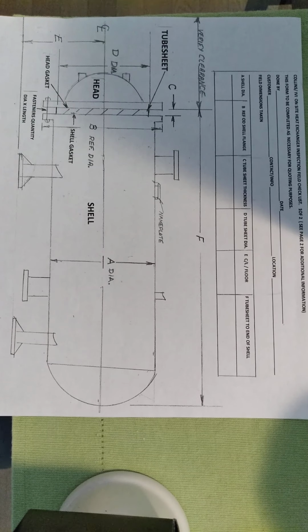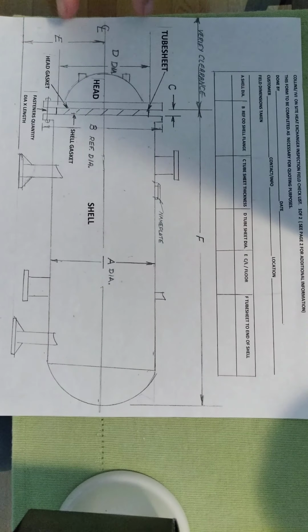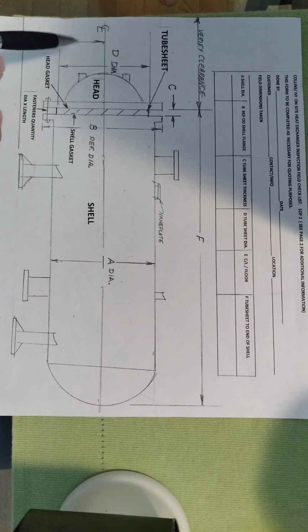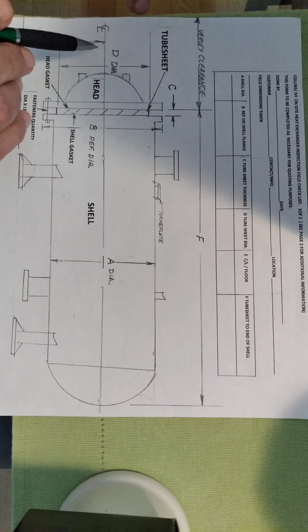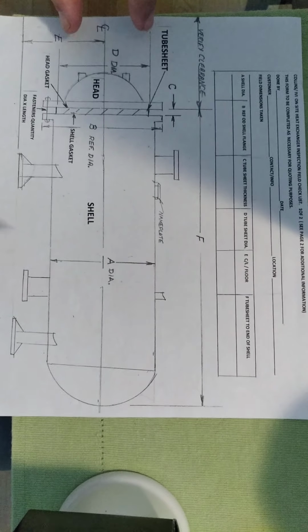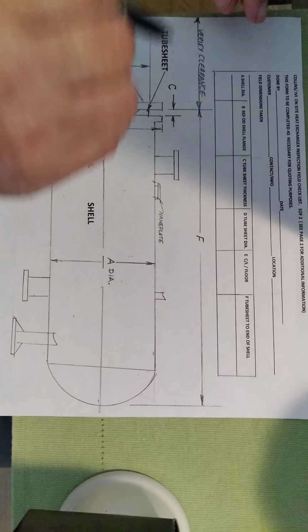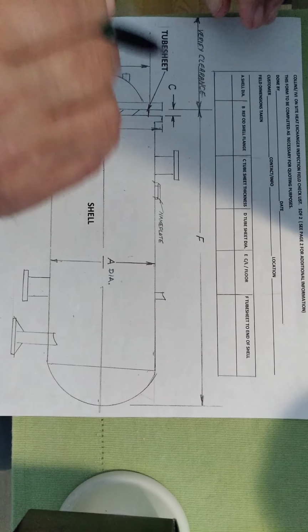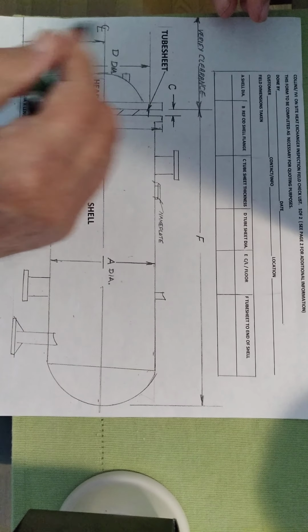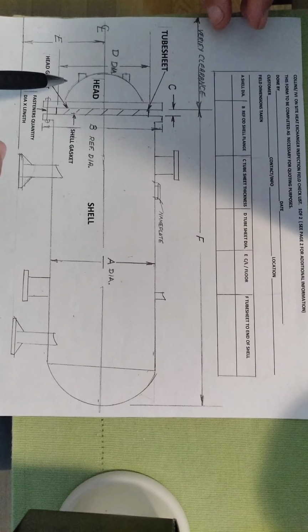Now, one other thing that could be a result, you have to look at whether or not this bundle can be removed without obstruction. Verify your clearance. There could be a wall that was built or some other items that were installed that eliminate the ability to physically remove that bundle because there's not enough clearance. It's coming out from right to left in this picture here. So make sure there's enough clearance to get the bundle out. If anything else has to be removed, we have to either quote that or the customer has to remove it in advance of us being there.